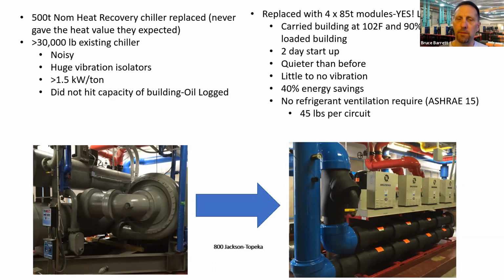Absolutely quieter than the previous machine. They're able to lease out space in that penthouse now, next to that penthouse, not nearly the vibration. Much, much quieter as well. 40% energy savings right off the bat. Braze plate, even though they do have an oil component, they do not oil log like a shell and tube machine does. So fantastic change out. Great piping job there, by the way, too.